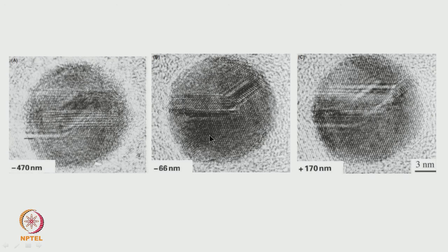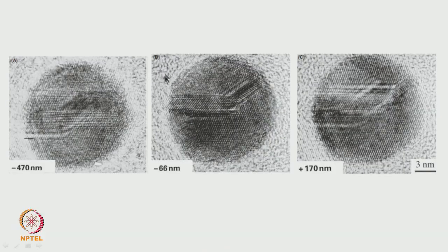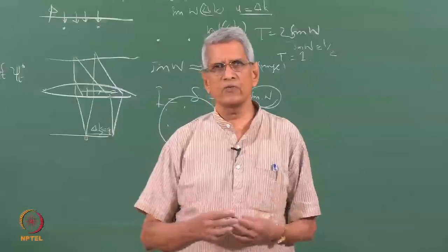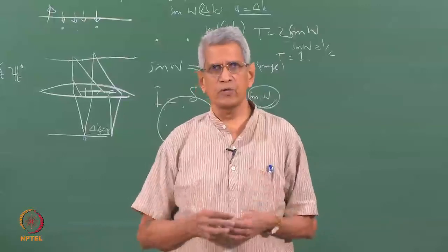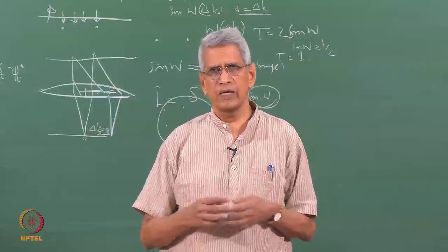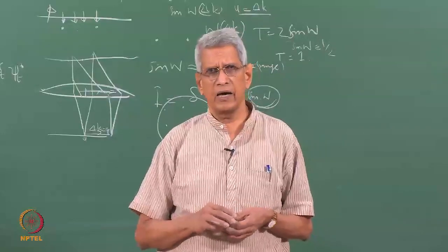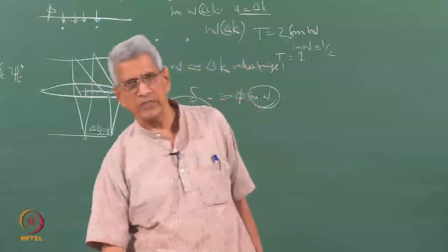So, when we do high resolution imaging, we should always try to take the image at Scherzer defocus. But so far, what we have done is a derivation to find out what the Scherzer defocus is. Depending upon the microscope conditions, the sample thickness, and at what voltage we operate it, these conditions can change.